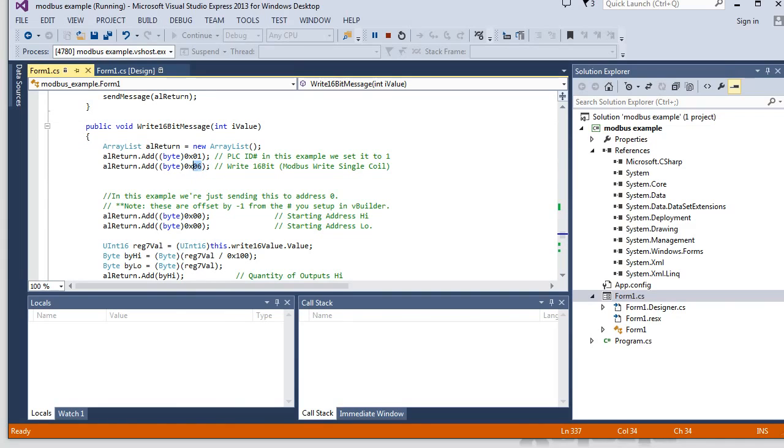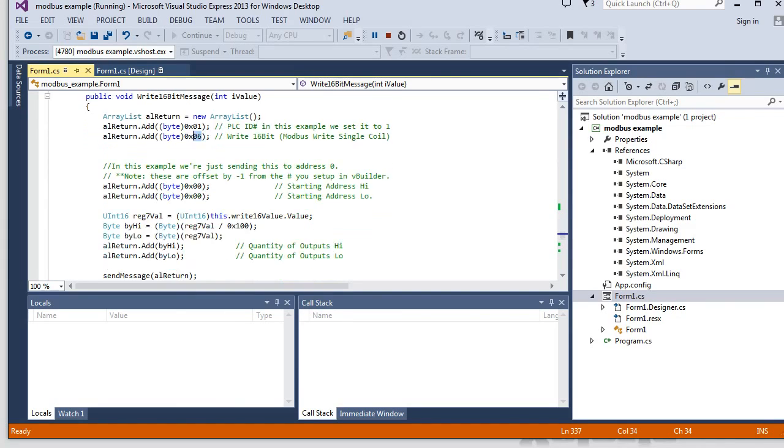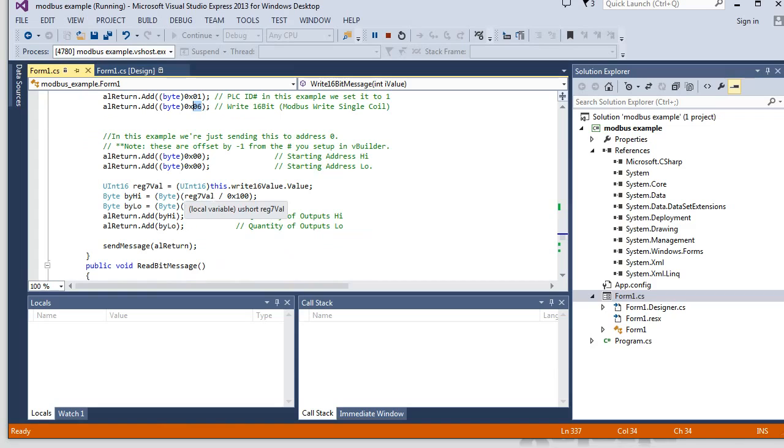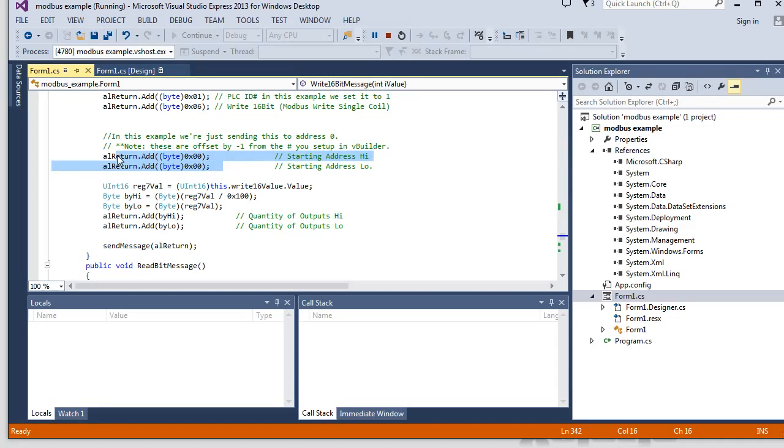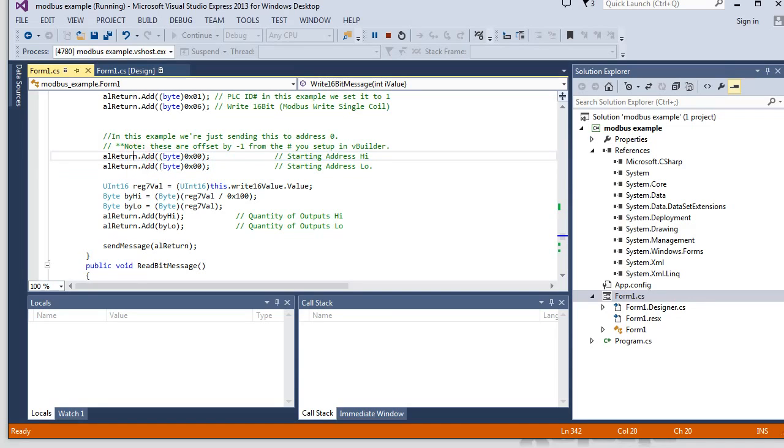And it does the same PLC ID, but its command is a type 6. And what you're just doing is you're going to be writing to the address zero. Again, it was address one in vBuilder. But we have to decrement by one for here.